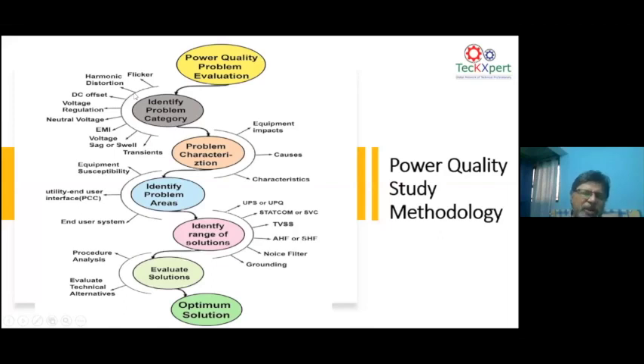So you have to look into the power quality criteria or the characterization of power quality, as I said at the beginning, in IEEE 1159, and accordingly use a good power quality analyzer at the areas where the problem is identified. That means problem characterization and identification of the problem area go together. Now you identify there's a power quality problem, let's say it's a neutral ground voltage. So we have to see which area has the neutral ground voltage problem, and then you connect the analyzer and characterize the problem.